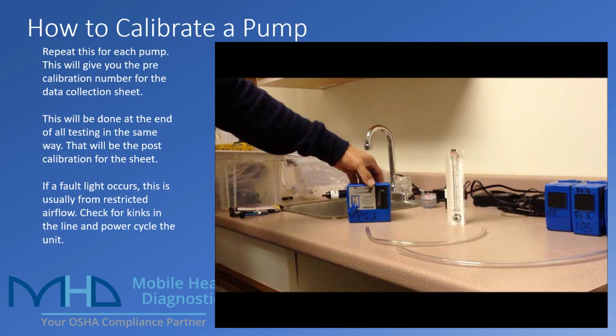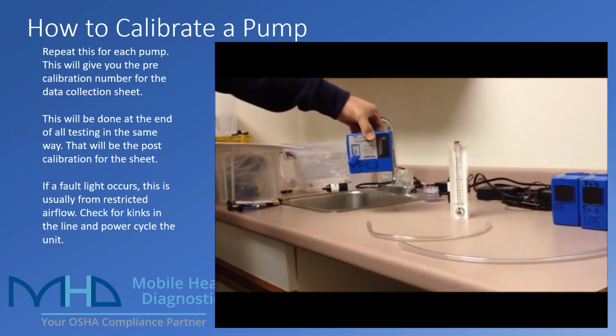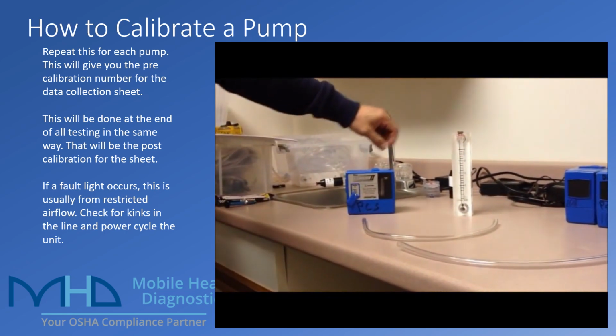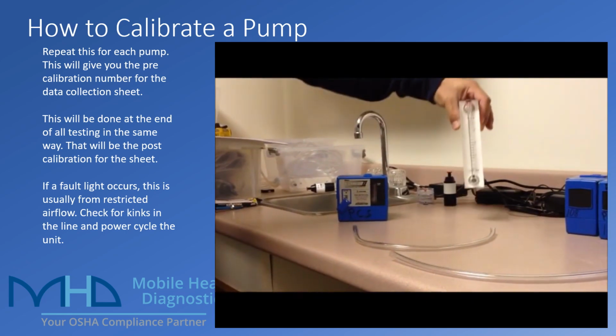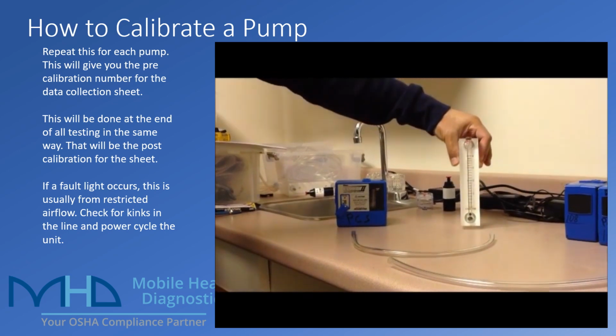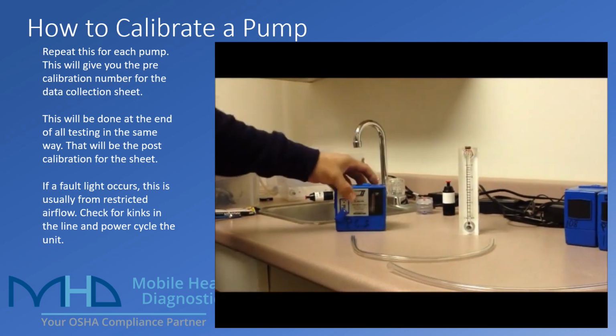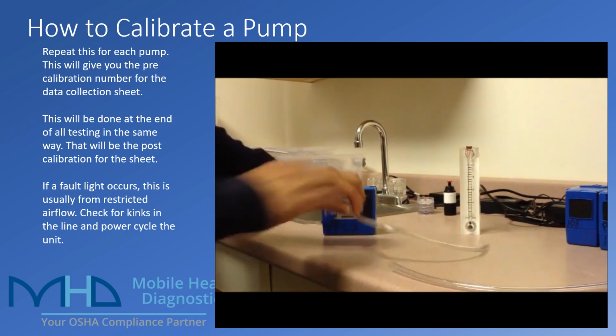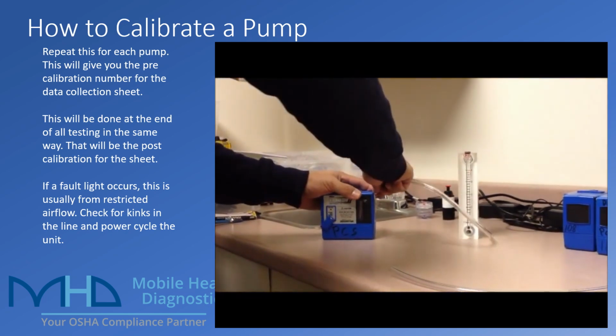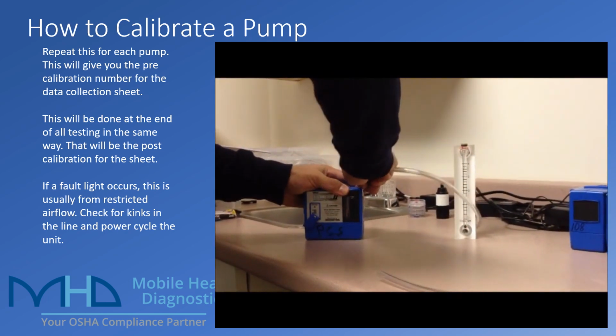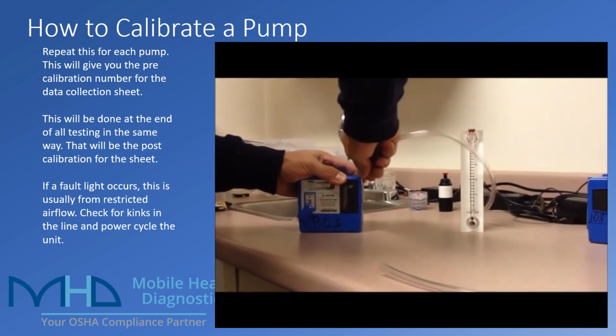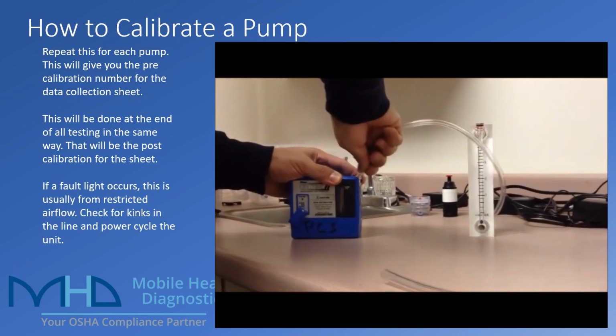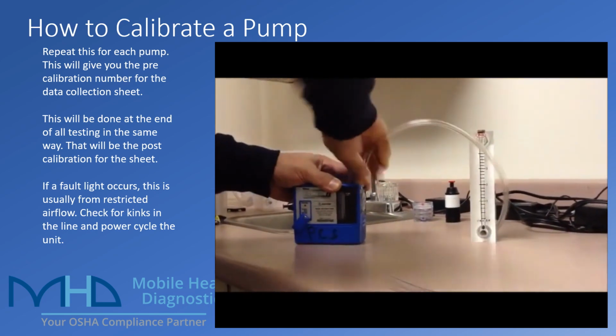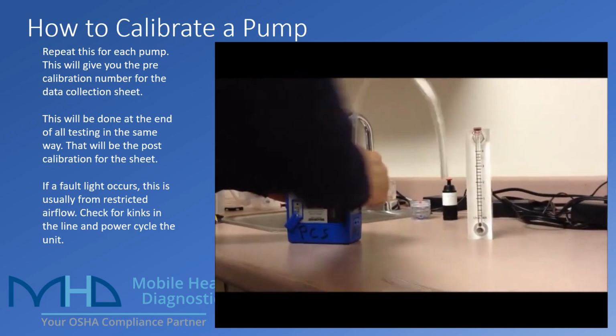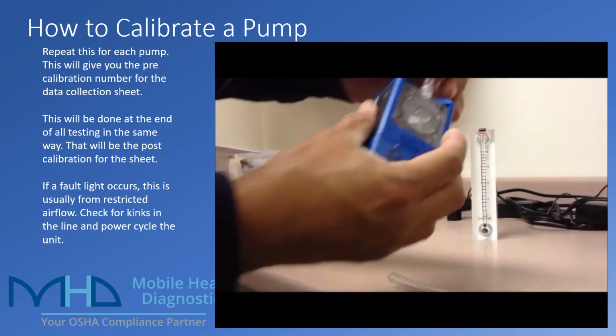So here we have a video that's going to quickly demonstrate how to set up a pump for calibration. We've got the pump with the battery switch exposed, as well as the analog calibrator here. And you'll just need some section of vinyl tubing. That vinyl tubing is going to connect to the intake port on the actual pump. You're going to want to make sure that there's a good secure fit on that. It should be self-sealing, where it doesn't need a C-clamp.